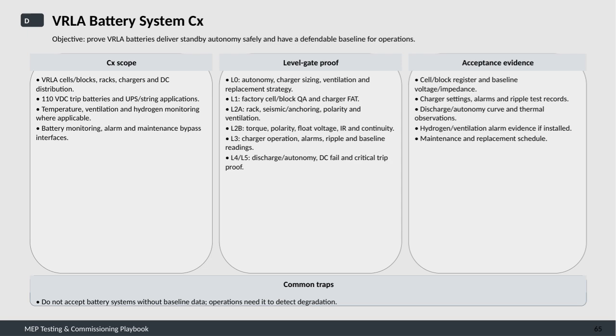Verifying a rack setup, including seismic anchoring, polarity, and ventilation, and checking torque, polarity, float voltage, insulation resistance, and continuity. Level 3 focuses on testing charger operation, alarm functions, ripple, and establishing baseline readings. Finally, levels 4 and 5 confirm discharge autonomy performance, checking for DC failures and critical trip functionality.